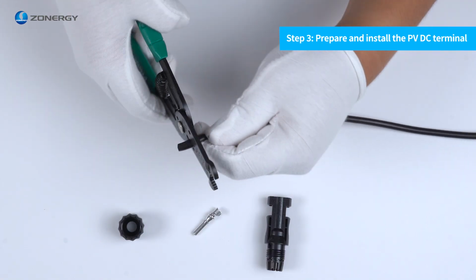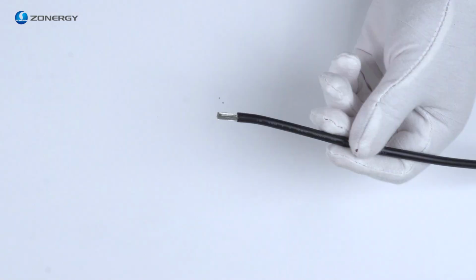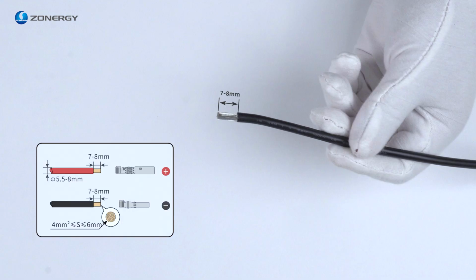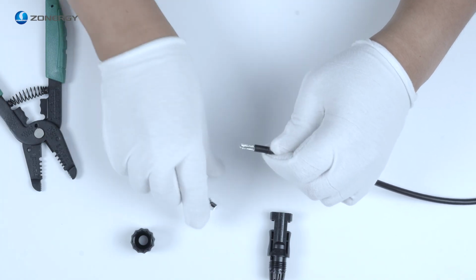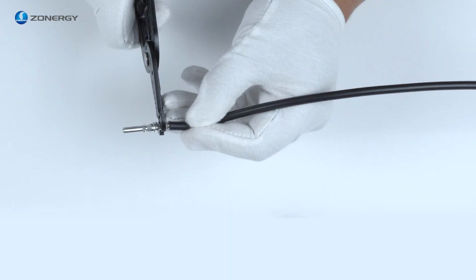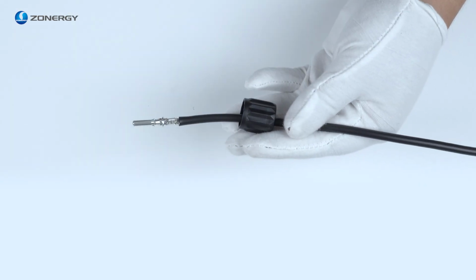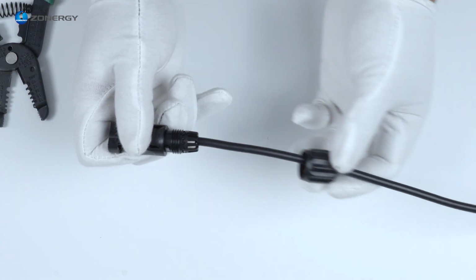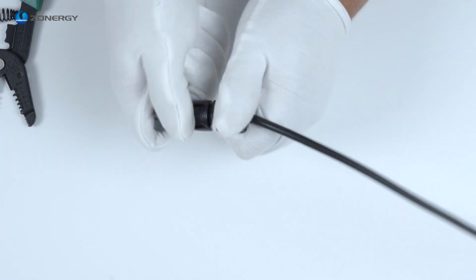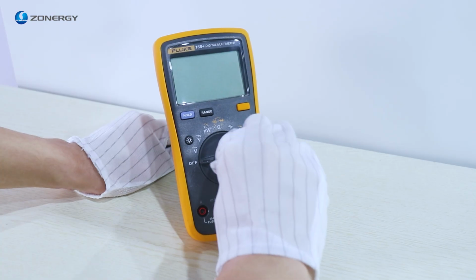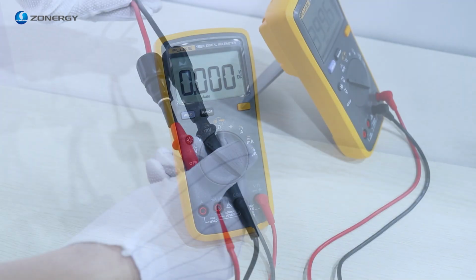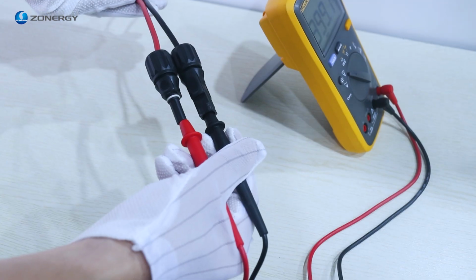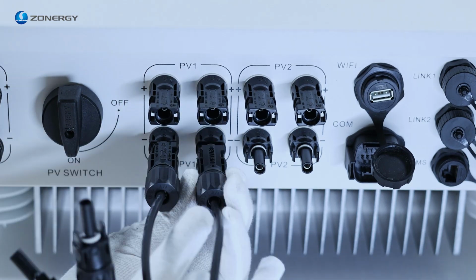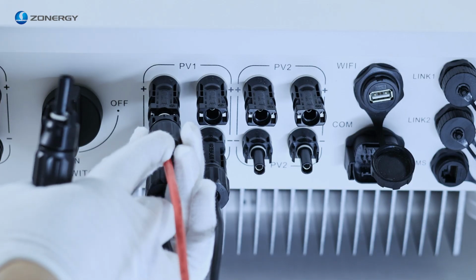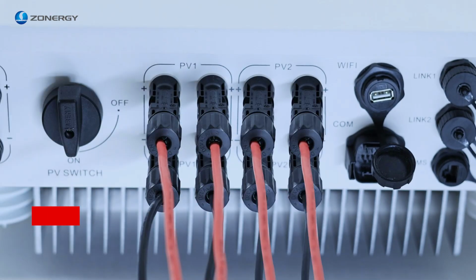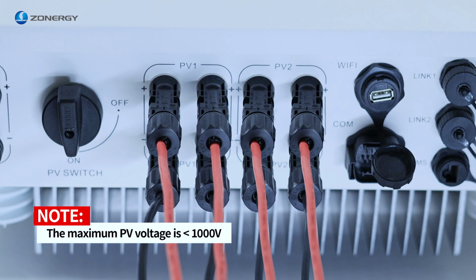Step 3. Prepare and install the PV-DC terminal. 1. Make cable joints of appropriate length according to the mark. 2. Connect the positive metal terminal with the positive cable. Clamp the terminal, pass the cable through, insert it into the connector. Tighten the screw, and do the same for the negative terminal. 3. Through the multimeter, check whether the positive and negative PV poles are correct. 4. Connect the PV DC input line to the inverter. Hear the click sound, indicating that it is in place. Note, the maximum PV voltage is less than 1000 V.